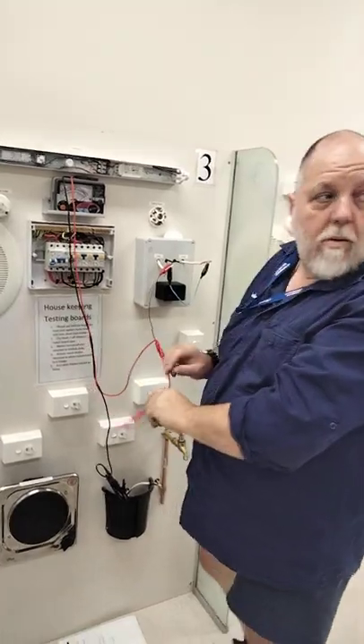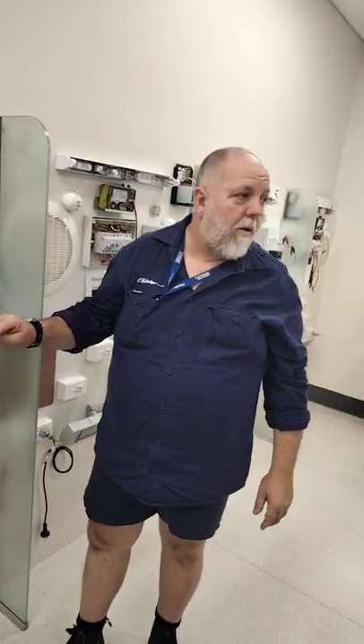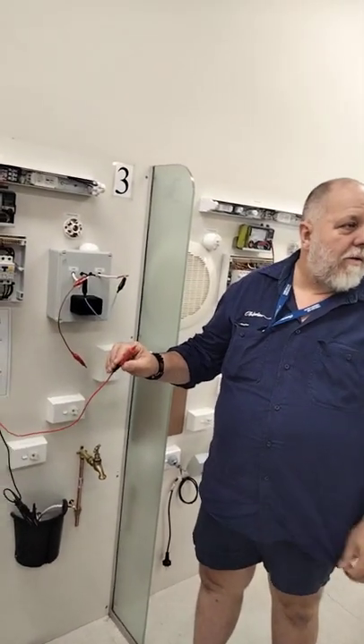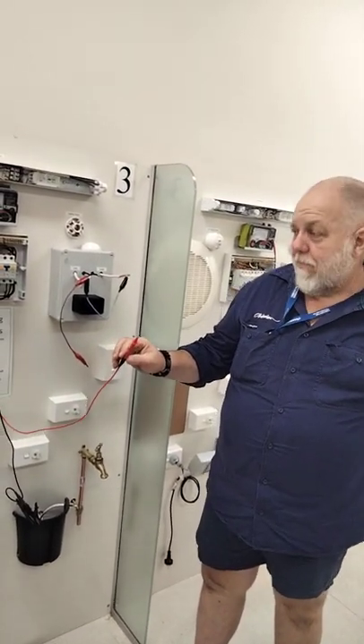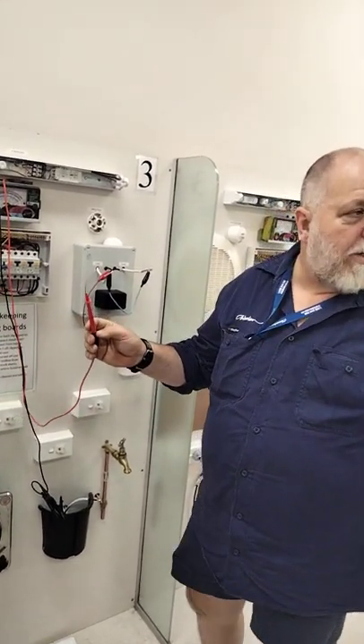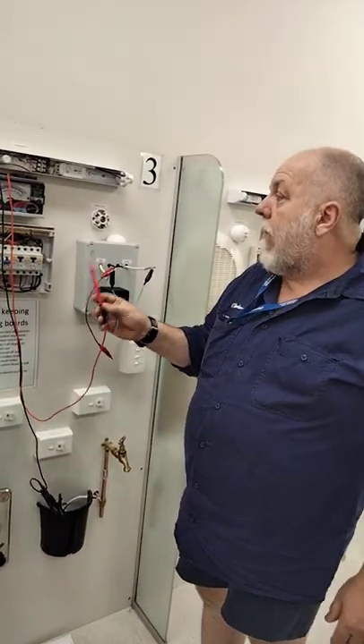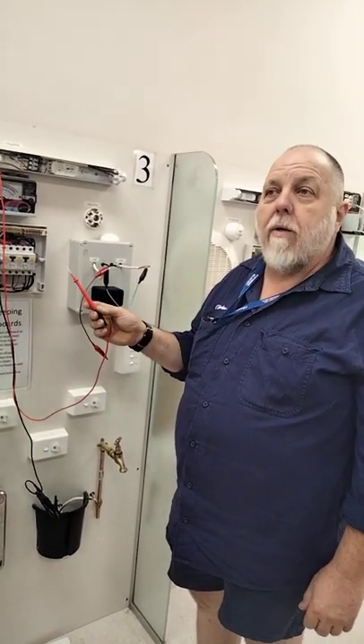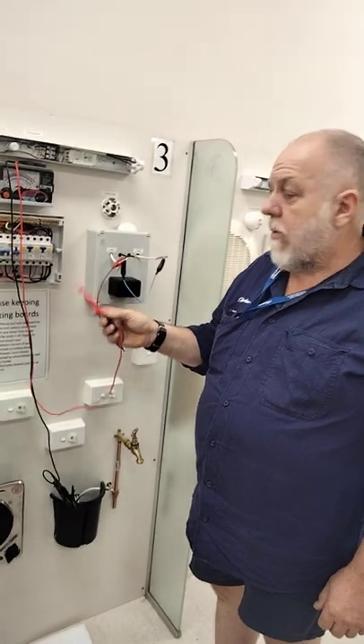What do you do in a real-life application when you can't test between the top of the board, the breakout, and the pit? You run a trailing lead out. That's what we were saying about zeroing before — you have to run a trailing lead out on an earth wire. So we've got that the active is faulty, but the neutral is okay.